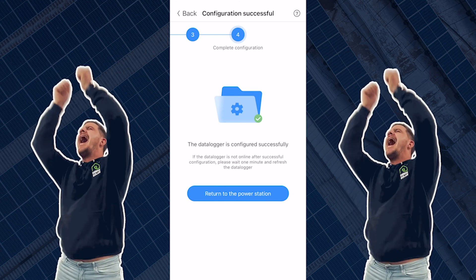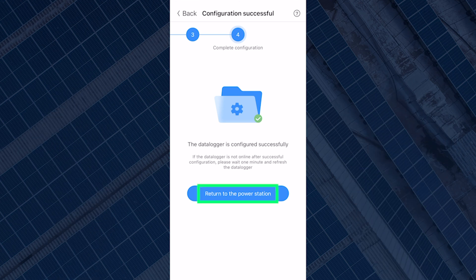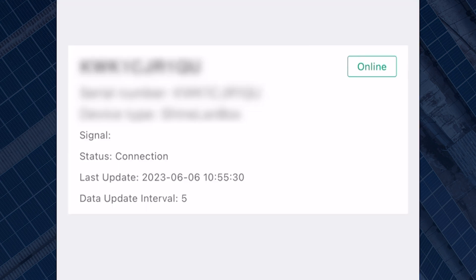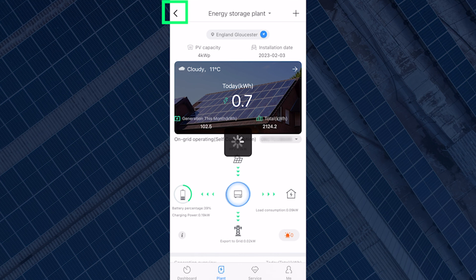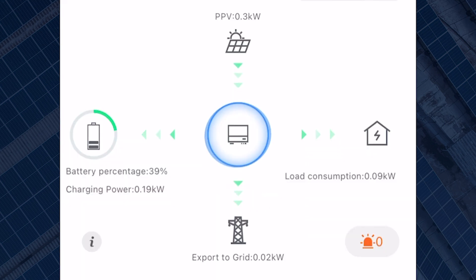If configuration is successful, then you can return to the power station where the ShinePhone will start to display the data from your inverter. As you can see, the data logger status has now gone from offline to online and on the plant page, you can now see the inverter data. The dongle should show a flashing blue LED to show a successful configuration.